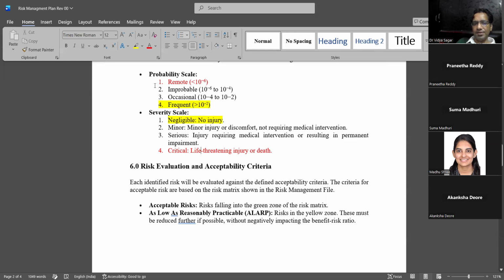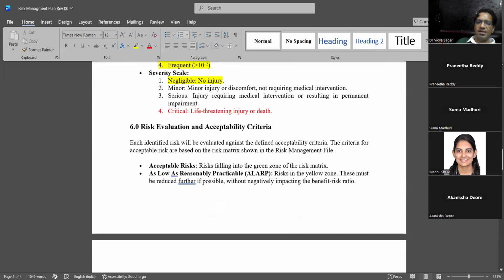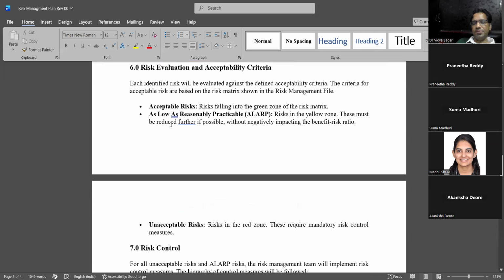So you need to write probability into severity. What is the quantifiable number? Then you apply risk controls. Before that, you need to do the risk evaluation and set acceptability criteria. How much do you need to bring it down? What is acceptable risk? I'll show you different methods of risk evaluation, I said quantitative, semi-quantitative, hazard analysis, FMEA and all that. I'll explain in my lecture notes. But you need to bring risk as low as reasonably practicable.